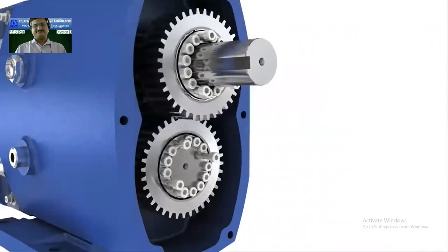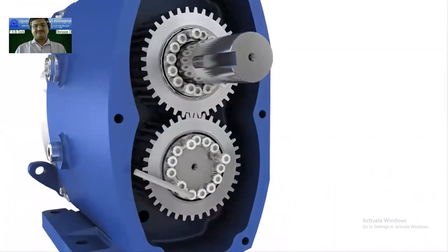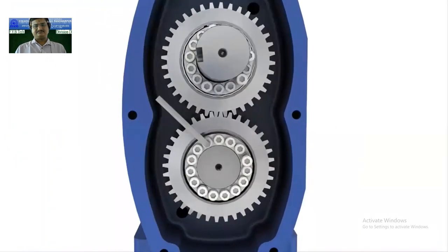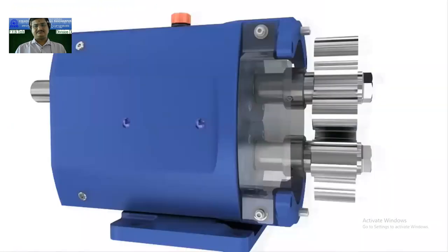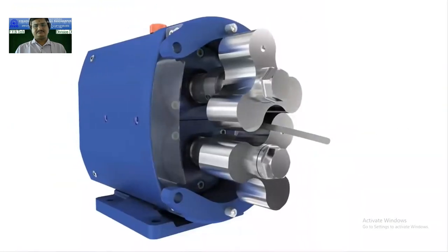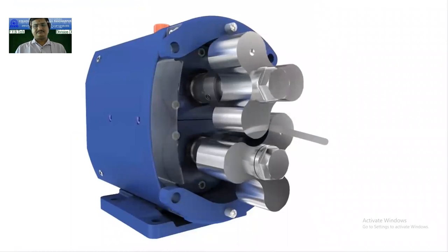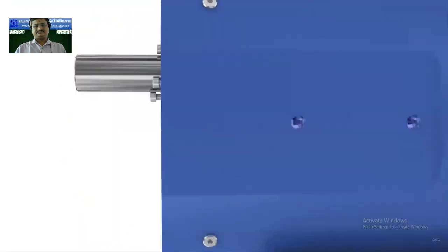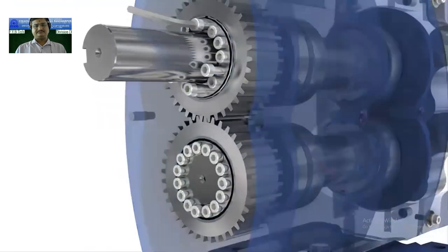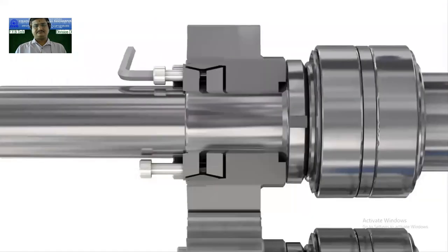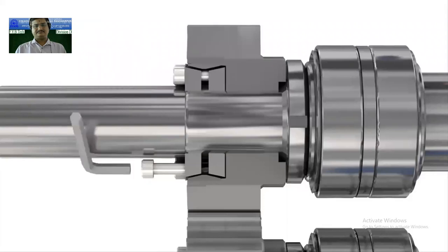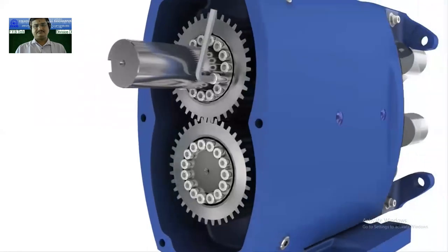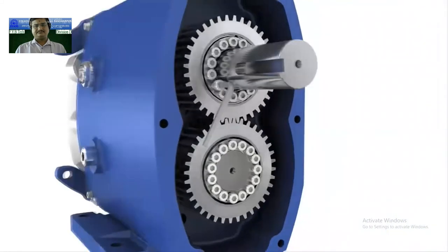The SRU features the taper lock timing system. This system allows quick and easy synchronization of the rotors, highly simplifying the timing procedure and reducing maintenance cost. By simply tightening a few screws, the gear and shaft are securely locked together. Also, with the elimination of keyways, users can benefit from increased pump life.